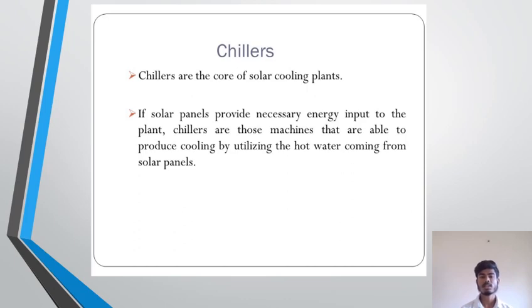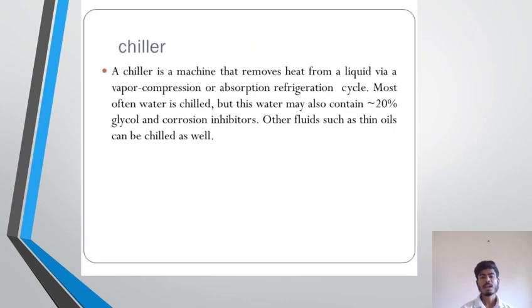And one more is chillers. Chillers are the core of solar cooling plants. If solar panels provide the necessary energy input to the plant, chillers are those machines that are able to produce cooling by utilizing the hot water coming from the solar panels. A chiller is a machine that removes heat from a liquid via a vapor compression or absorption refrigeration cycle. Most often water is chilled, but this water may also contain 20% of glycol and corrosion inhibitors. Other fluids such as thin oils can be chilled as well.